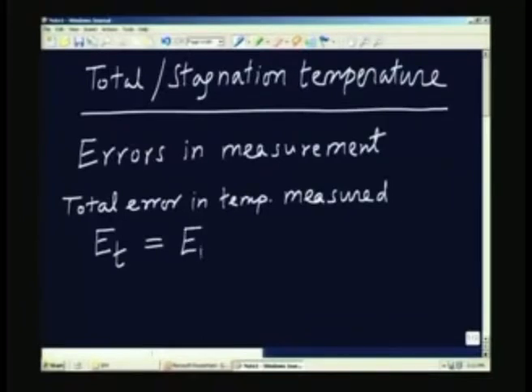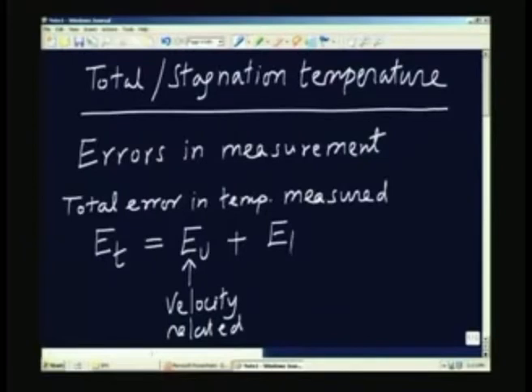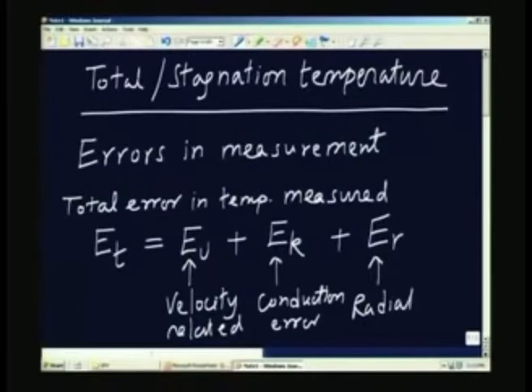The first component is the error due to the velocity of the fluid, or velocity-related error. Then there could be error due to conduction, which we call Ek — the conduction error. And thirdly, we have the error due to radiation, Er. So there are three components to the error in the measured temperature.